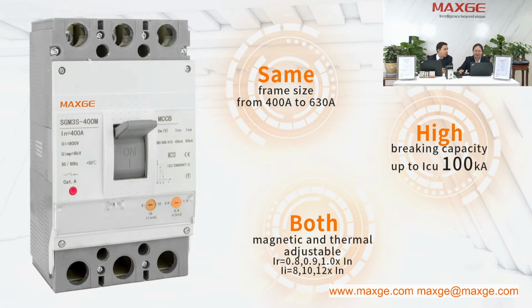And we have a very good advantage with respect to the other competitors, that we have a very compact frame. For the 400 and the 630 it is the same frame size. Again, the frame size is reduced by 21%. The volume is reduced with respect to the earlier frame size, but still keeping the performance the same, and the capacity is much higher. Like in a 55-degree environment, our temperature rise can pass very easily. That's very good for the customer's choice. And they have much more choice for the distribution box, because we have the smaller size.